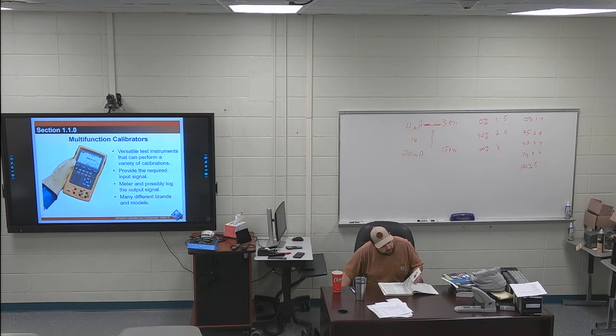Even going into the next page, the whole paragraph's highlighted. Instruments used for calibration must themselves be calibrated in reference to an accepted standard. In most cases, for calibration to be valid, the instruments must be traceable to a national standards body such as the National Institute of Standards and Technology. Normally, instruments are sent away to a calibration lab on a scheduled basis. A calibration sticker on the instrument and a matching certificate confirm the calibration and traceability status and show the date of calibration. Calibrations then performed using those instruments are deemed to be both valid and traceable.